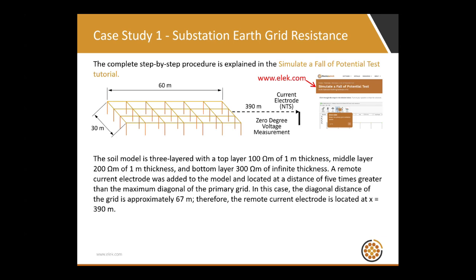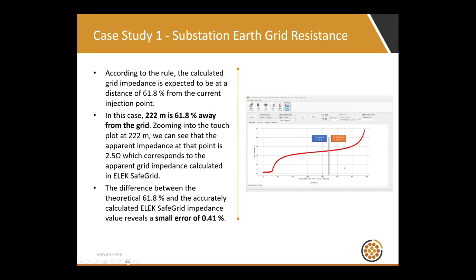Actually, I looked at this presentation earlier, and it's not actually 5 times the distance. So I'll need to ask the engineers how they actually did this, but it's actually more than 5 times the diagonal distance. The diagonal distance is 67 meters, and 5 times that is actually not more than 390 meters. But that's kind of irrelevant. So we set up the test in the software, and we were able to model this apparent impedance curve.